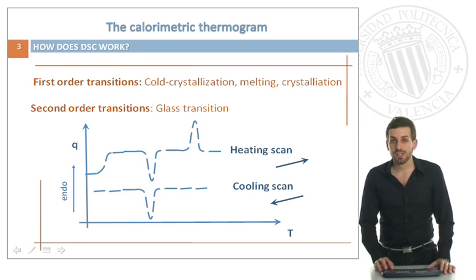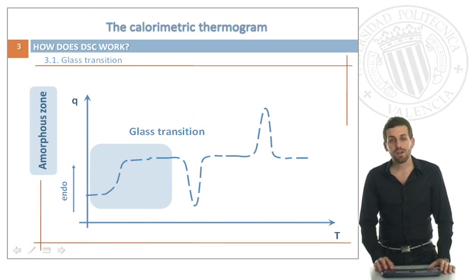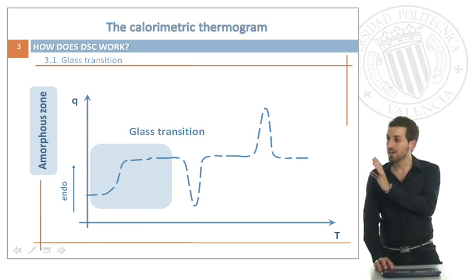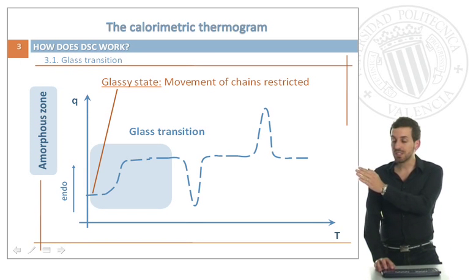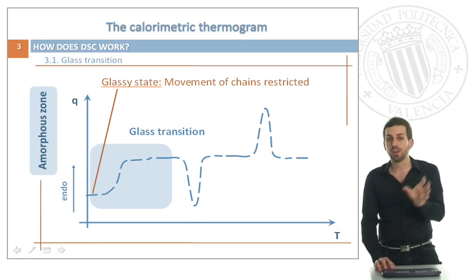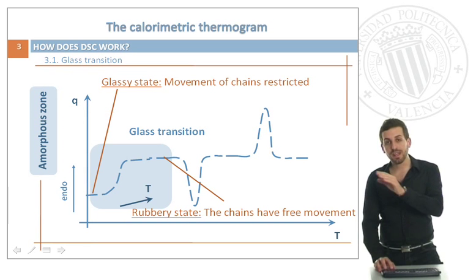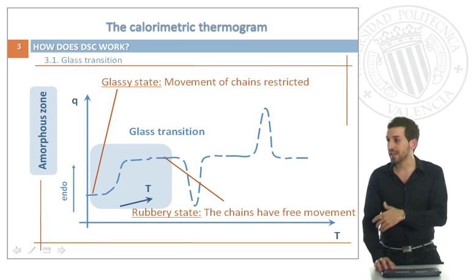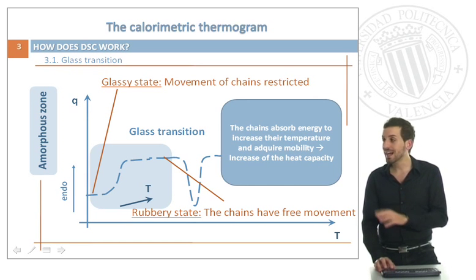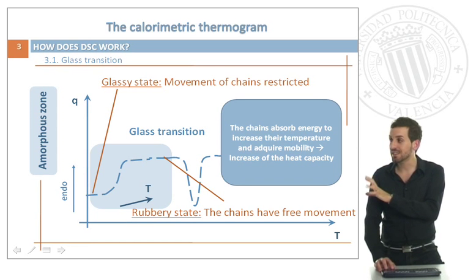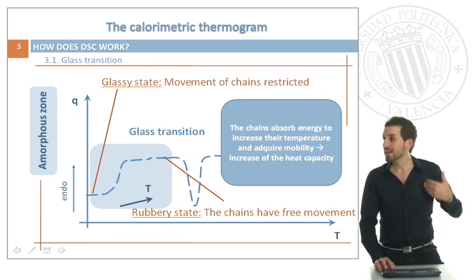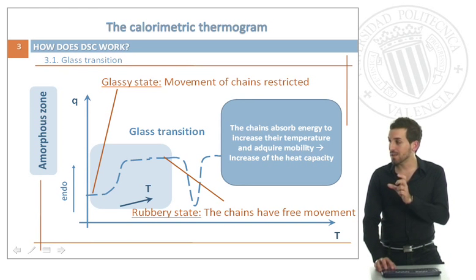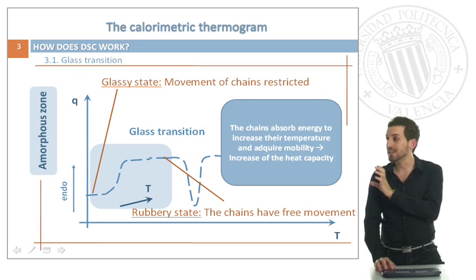This is the summary of the transitions that we can see. How does our DSC work? We are going to start with the amorphous zone and the glass transition. At ambient temperature we have our polymer in the glass state, which means that the movement of the chains is restricted. As we increase the heat, we will obtain a solid polymer in the rubbery state, meaning the chains have free movement. What has happened in our DSC is that the chains are absorbing energy from the DSC to increase their temperature and therefore acquire mobility. This will be seen in the response of our DSC as an increase of the heat capacity.